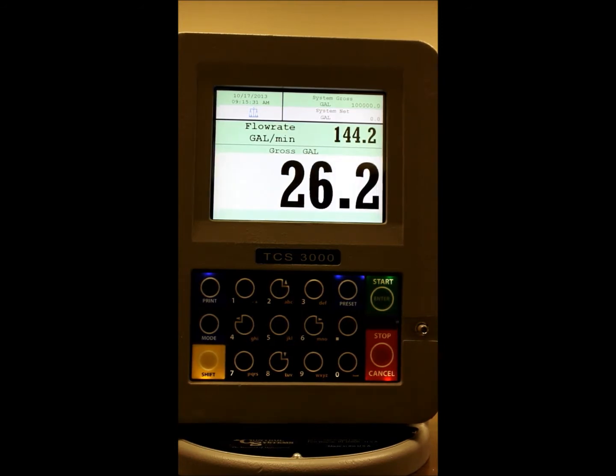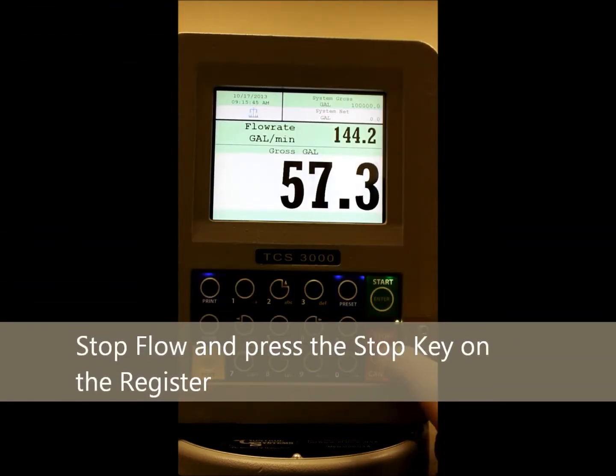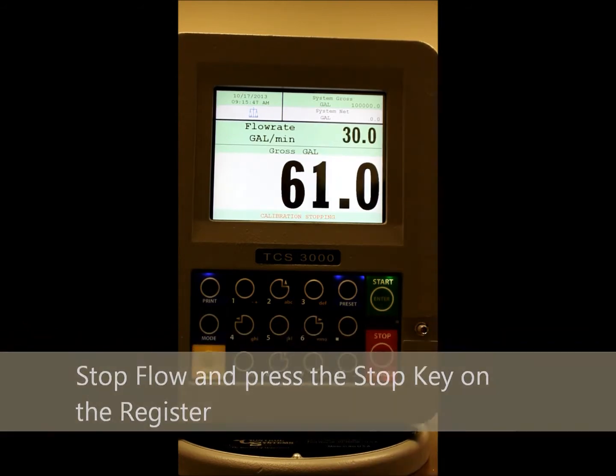As the register is counting the gallons going into the prover, note that the gallons on the register may not be accurate as it is not a calibrated product currently. Once the prover hits the mark, the 100-gallon mark, you will push the stop key down, which will stop calibration on the register.